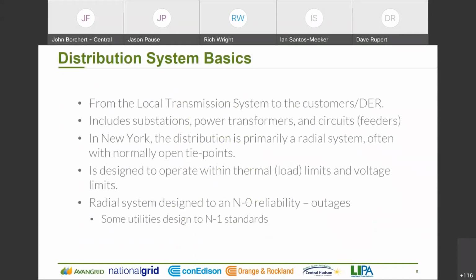The distribution system is defined as the system between our transmission and the customer. It includes substations, power transformers, and circuits or feeders. In New York, the distribution system is primarily a radial system, often with normally open tie points. It is designed to operate within thermal and voltage limits, and is typically designed to what we'll call N-0 reliability, meaning a single element out on the distribution system can result in a customer outage. Some areas have a more robust design and reliability criteria, typically based on customer concentration. The distribution system is inherently different than the transmission system, and therefore uses different planning models and processes.